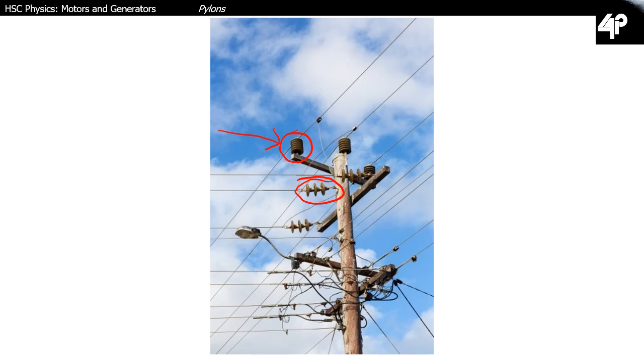Like I said, you're going to find them on the wooden telegraph poles, or sometimes those poles are made out of concrete as well. So these insulators can be similar to the strain or suspension insulators that you see on pylons, and quite often they do follow that 11 kilovolt per disc rule. So this one here, I could estimate that that is a 33 kilovolt line, because as you can see, I've got 1, 2, 3 discs in the stack. But what's different about these ones is that they don't need to be taking the huge mechanical strains like a pylon does, because these lower voltage lines are much thinner. The distance between the poles tends to be much shorter, and so this means that the lines are under less mechanical tension.